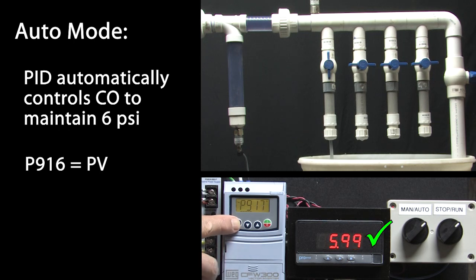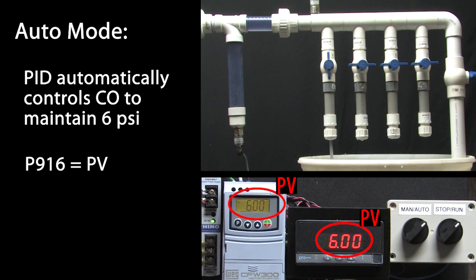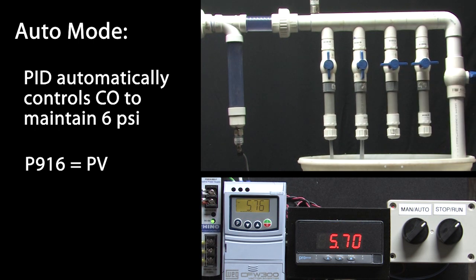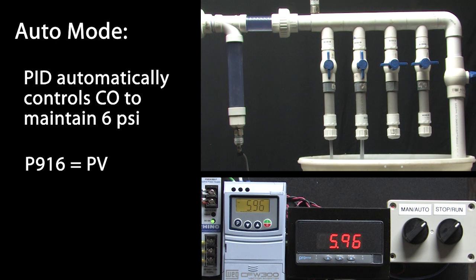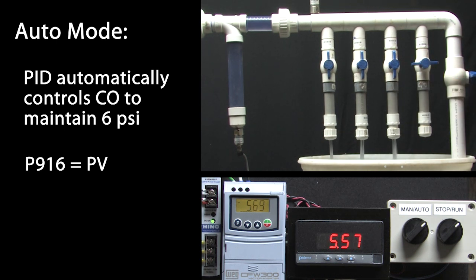And remember, you can also see the process variable in parameter 916. How about two valves? Wait a few seconds. And yep, it settles out right at 6 psi too.